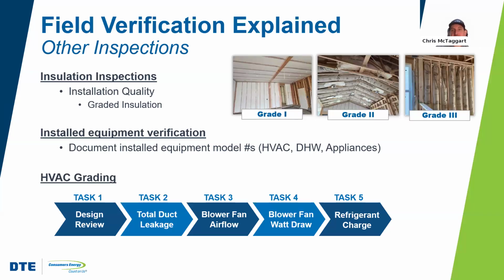The duct system is tested for tightness, total duct leakage. The blower fan inside the air handler is tested for airflow performance, and we can test the watt draw of the blower fan to see how efficient the air distribution is. Finally, there can be an evaluation of refrigerant charge, principally for air conditioning systems, but if you're installing heat pumps this is also very important, because heat pumps are very sensitive to refrigerant charge in the heating system as well.